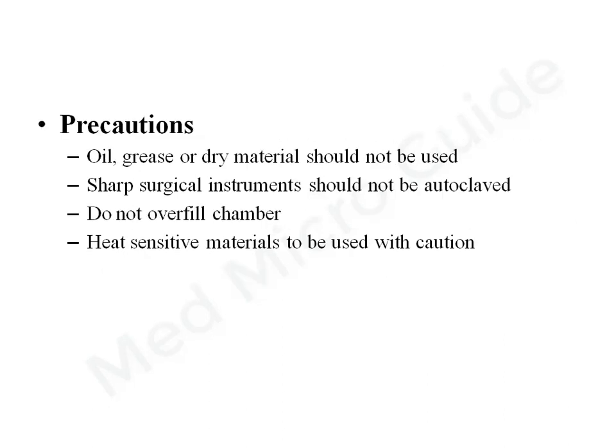Precautions when handling the autoclave: do not overfill the chamber; sharp surgical instruments should not be autoclaved as edges will be corroded by steam; heat-sensitive materials should be used with caution; oil, grease, and dry materials should not be autoclaved.